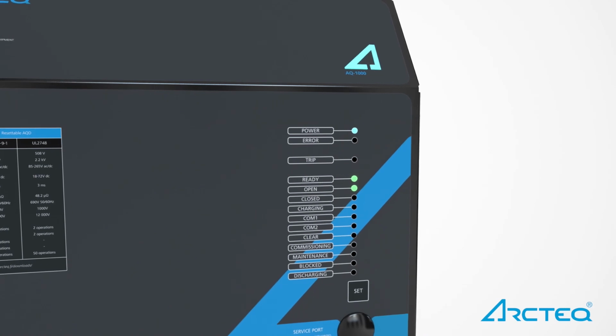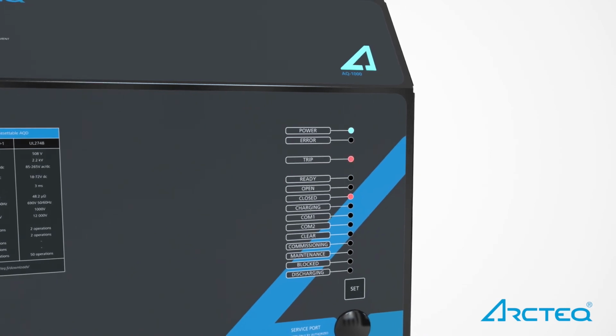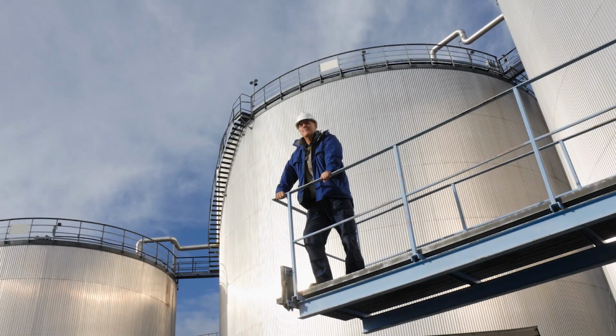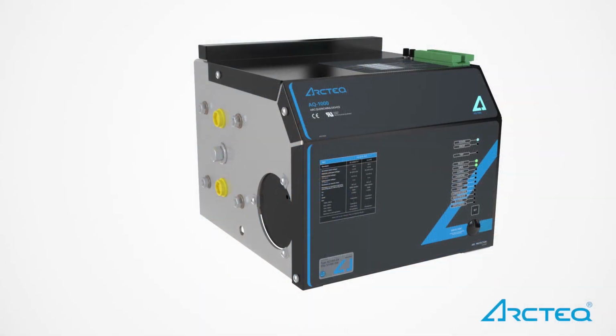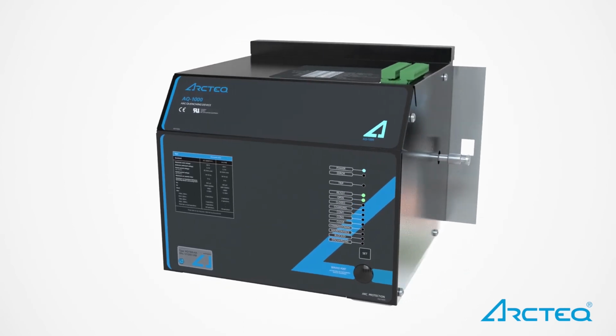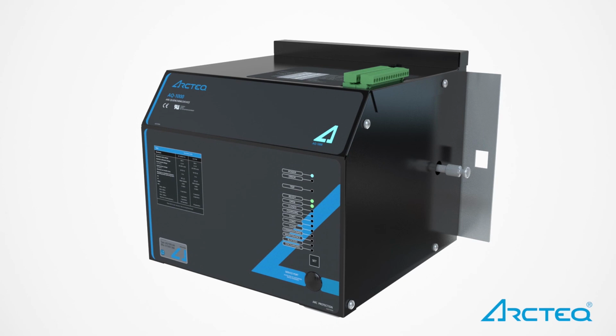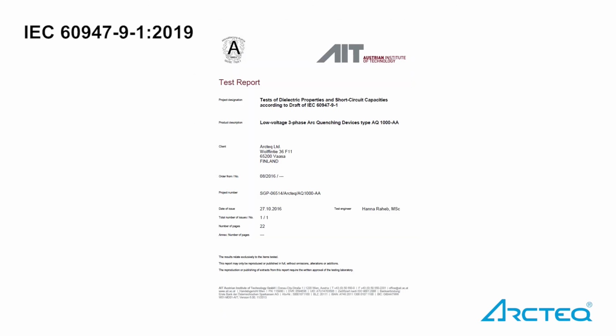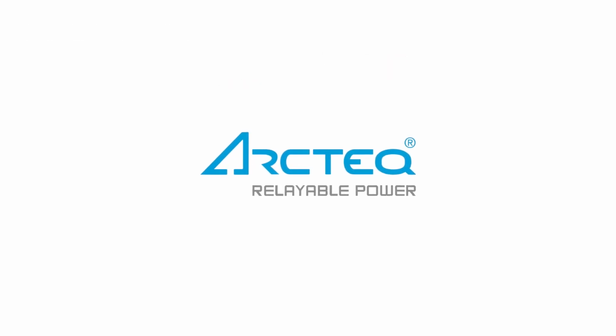The quenching device reusability and onboard supervision features raise the bar on system reliability to a new level, offering guaranteed peace of mind by the ultimate personal safety and return on investment in a single operation and plant lifetime. Less than 4 milliseconds arcing time keeps incident energy levels in less than 1.2 calories per centimeter squared, according to IEEE 1584. AQ1000 arc quenching device, tested and approved according to latest UL and IEC standards. Arcteq, the pioneer.